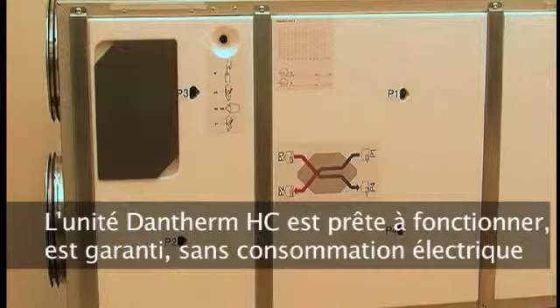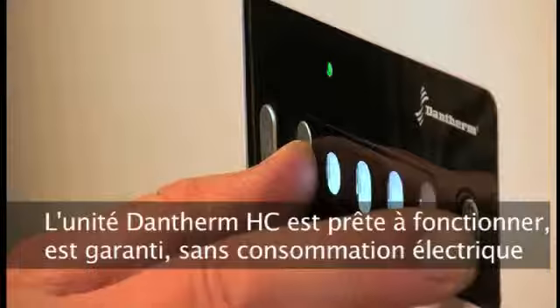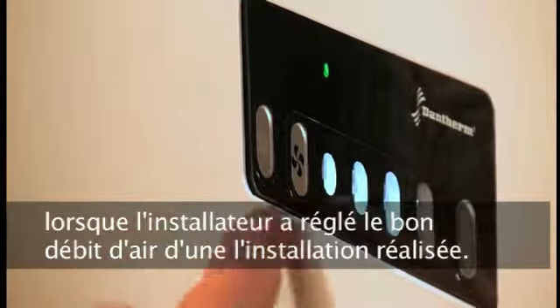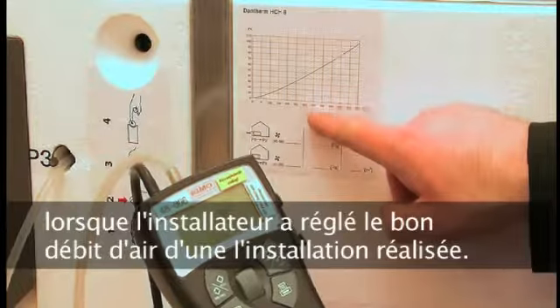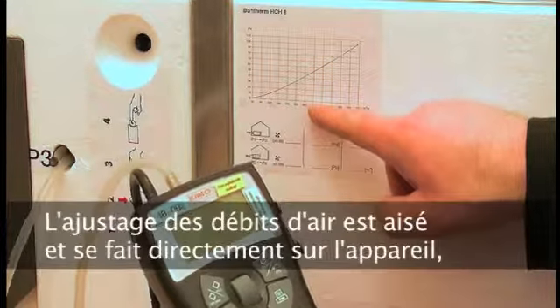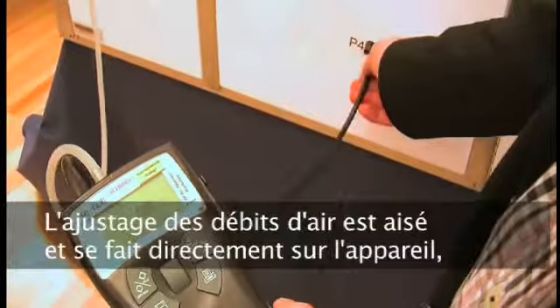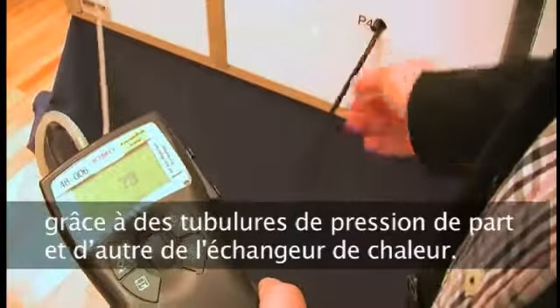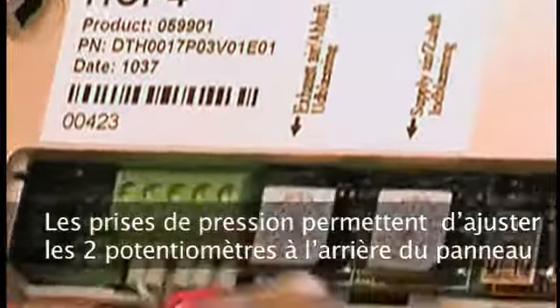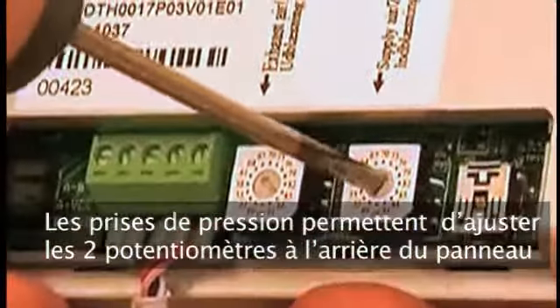The Dantherm HC unit is ready for operation when the installer has adjusted the correct air volume for the actual installation. Adjustment is easy and simple and takes place on the front of the unit, where the air pressure across the heat exchanger is measured. The measurements are used for final adjustment on the rear side of the panel.